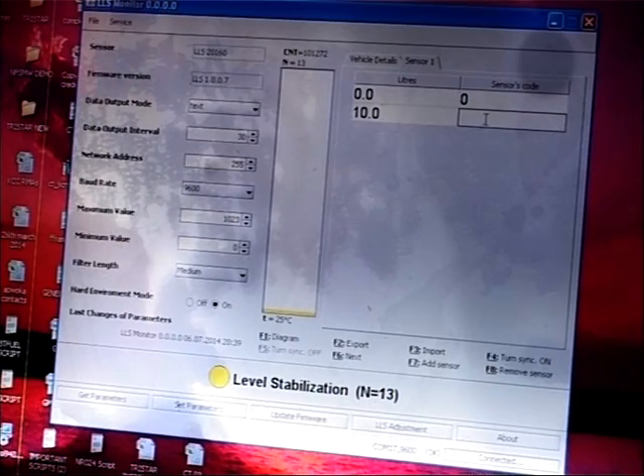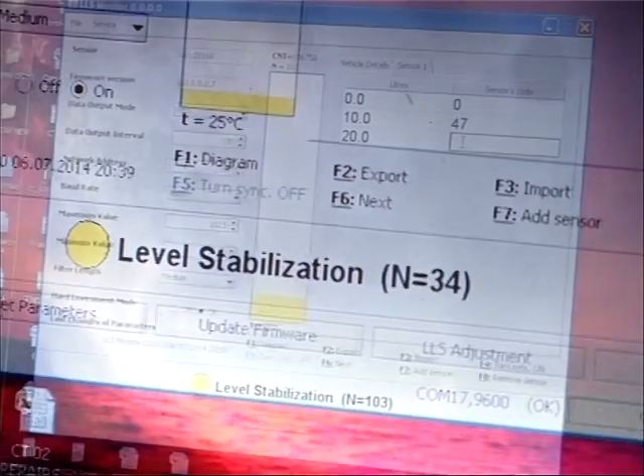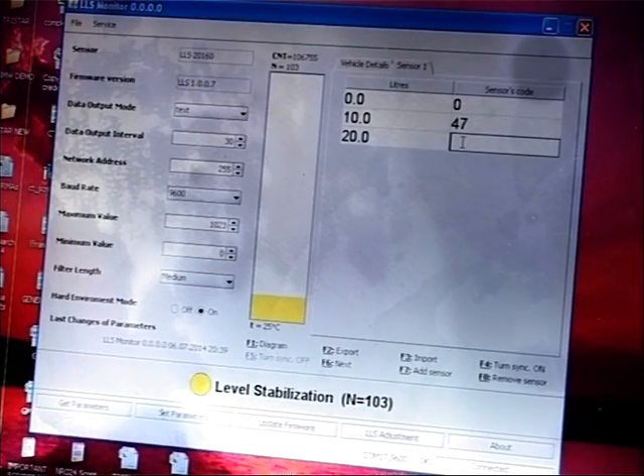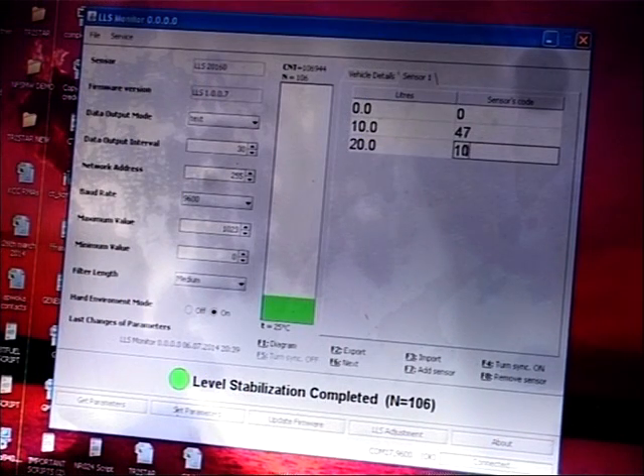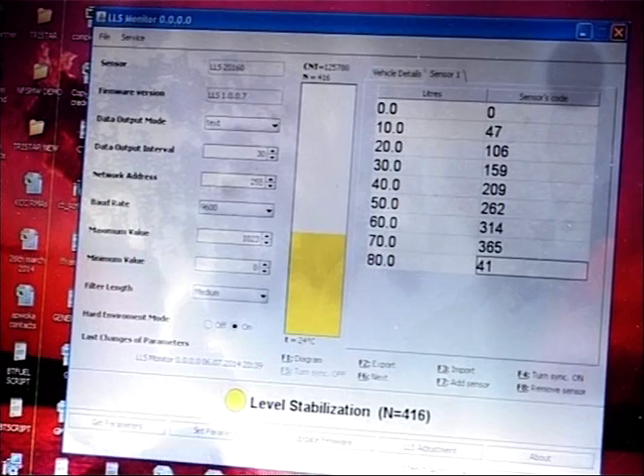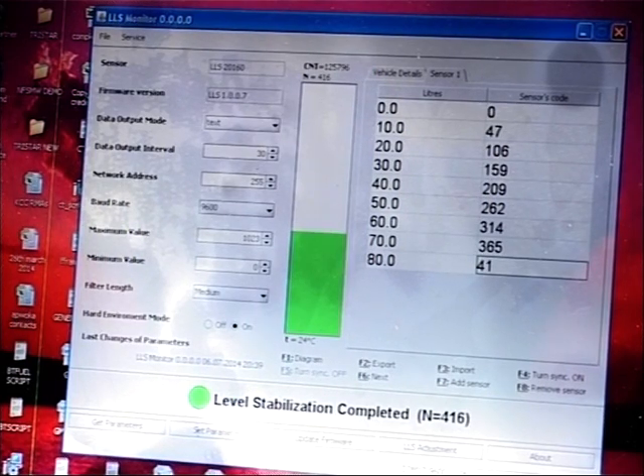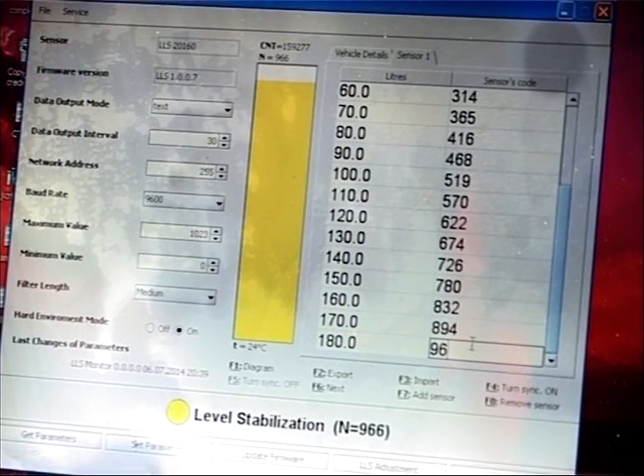Now on our computer, we have a platform that we use for calibration of the level sensor. After adding every 10 liters, the indicator at the middle of the screen will show yellow. At this point, the sensor is trying to get a stabilization code. After turning green, you give it a few seconds before a final value is entered. For accurate calibration, not less than 20 values should be entered, all the way until the tank fills up.